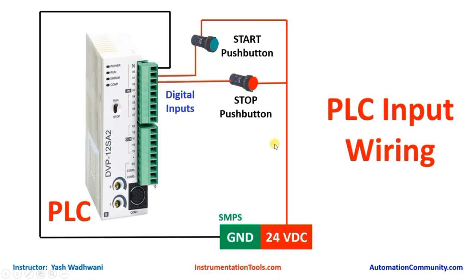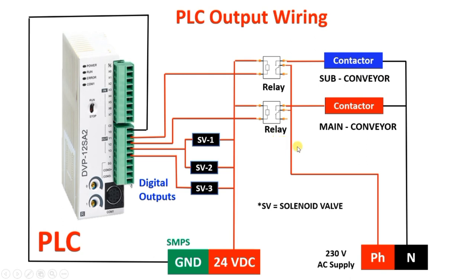We have a total of four outputs — two for the conveyor and two for the packing machine. Conveyors are motors and cannot be switched on and off directly from the PLC. We must use a starter with a contactor, which is energized by a relay, and the relay is energized by the PLC output. In the common terminal of both relays, we connect 230V AC supply.